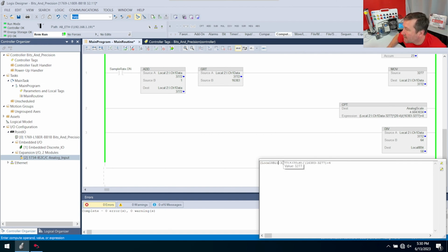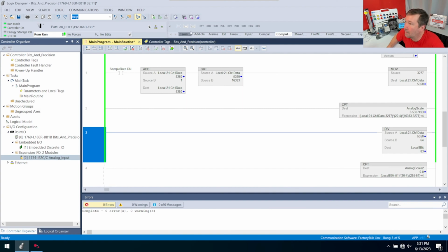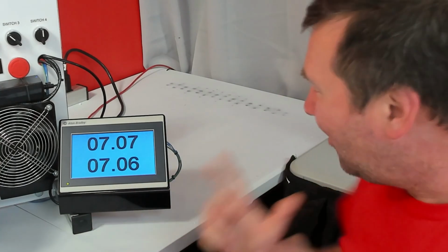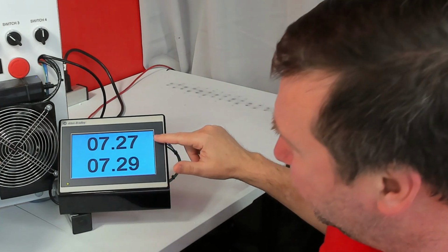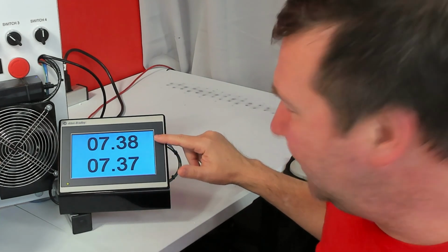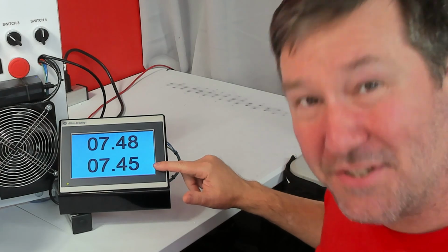And then in place of their 3277, that, remember, was the low value of our analog resolution. That is now going to be 51. Then the range of our analog signal is now going to be 255 minus 51. And we're going to put that in. And on the surface, they look pretty close. But if you notice, this one is climbing fairly consistently, and this one is jumping.